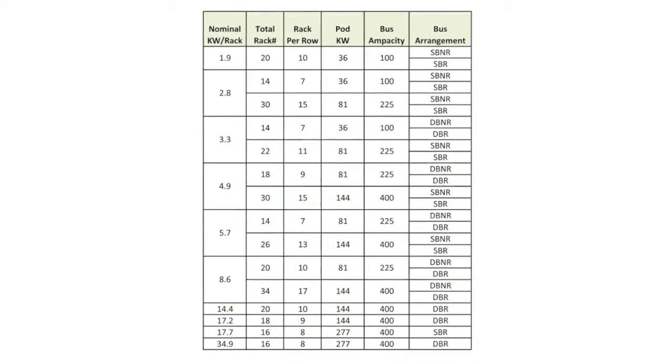On a more targeted level, when designing your rack, row, and pod arrangements, the following rules will help you effectively manage your costs. Calculate the number of racks in a pod using the kW per rack and kW capacity of the busway, as we demonstrate in Chapter 3 of our design manual. Whenever the calculated number of racks is more than one-half greater than an even number of racks, the racks used in the pod should be increased to the next even integer. It's rare to see individual racks utilized to their design limits, and increasing the rack count is beneficial to the end user. Using this methodology, we have found that the maximum number of cost-effective pod designs cover only 10 separate kW per rack ratings. When busway arrangements are also considered, there are only 25 pod arrangements that you should consider in your data center designs.